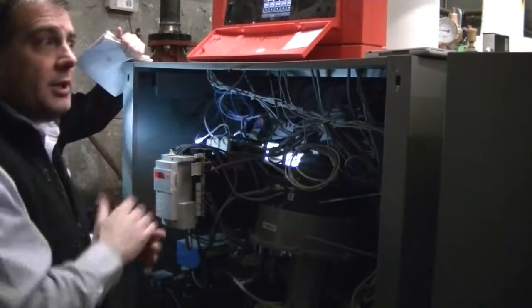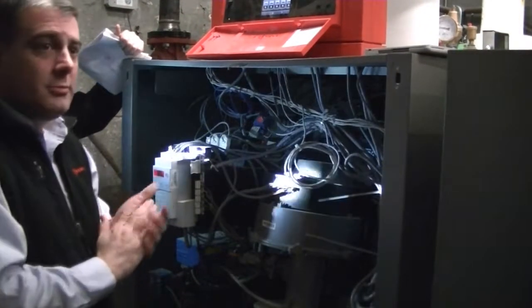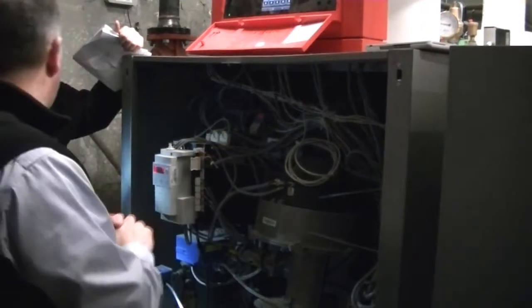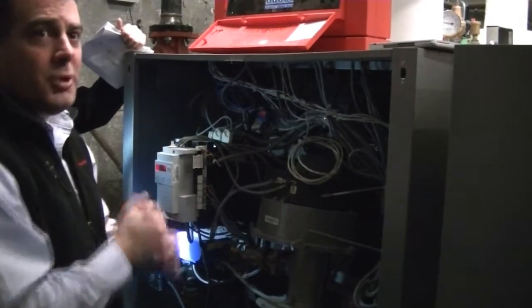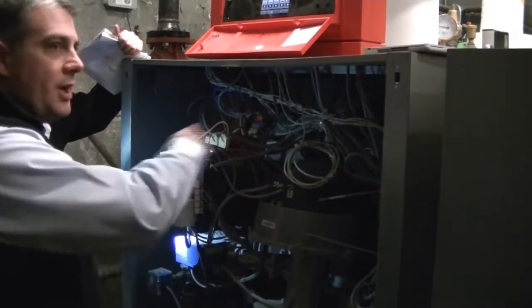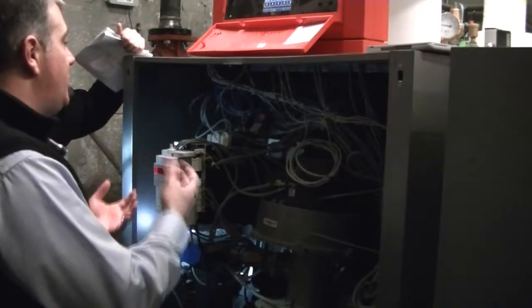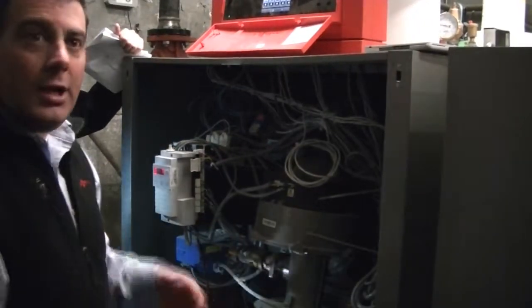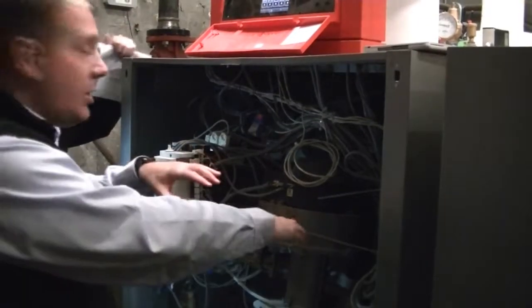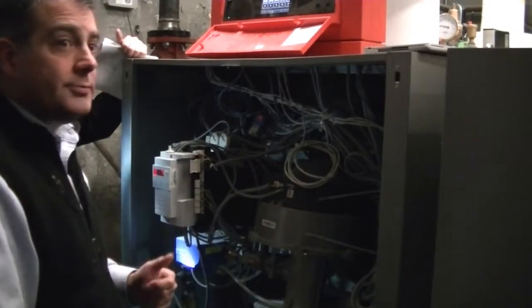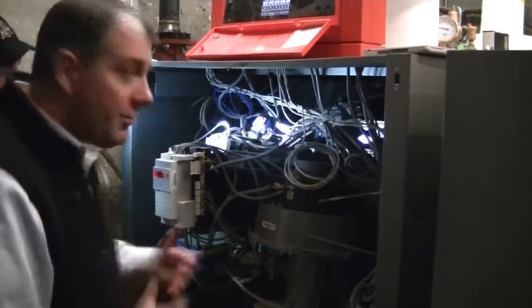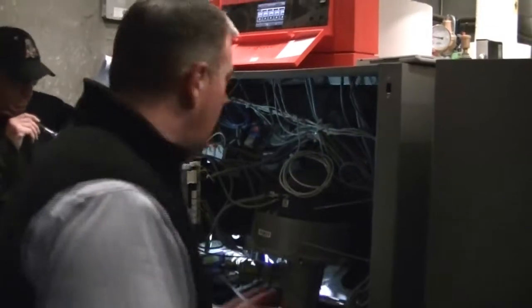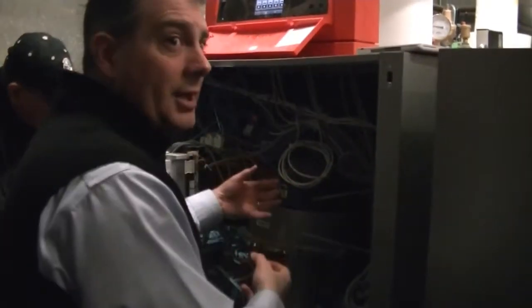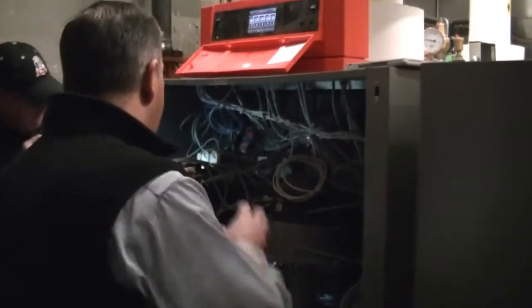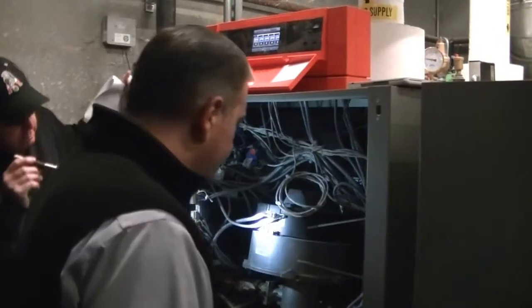So how do you clean it? You get a garden hose. There's a garden hose somewhere in the building you can connect to. You spray the inside of the chamber down with a garden hose. If you see any buildup of dust or debris on it, all that water will run down out through the condensate drain and out the back of the boiler. Okay? Very easy boiler to service and maintain. You don't have to take the burner off to get at the electrodes or the ionization rods. Everything is pretty accessible.